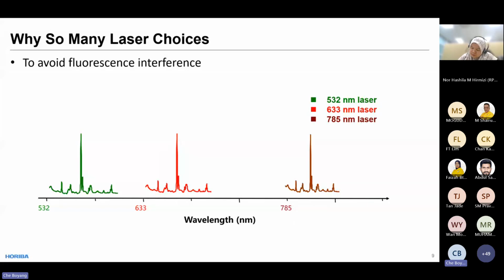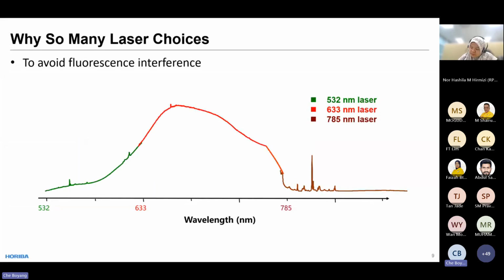However, in real life, what we usually get is this kind of result. You see a very strong background under the green and red lasers, and this background is caused by fluorescence. Raman is a relatively weak signal, but fluorescence is quite strong, so your fluorescence background will cover your Raman peaks. You will not be able to observe all the Raman peaks if the fluorescence is too strong. To solve this, we suggest using a laser with a higher wavelength, closer to the NIR. When we use this 785 laser, you can see the fluorescence is reduced, and we can see more Raman signals from the sample.